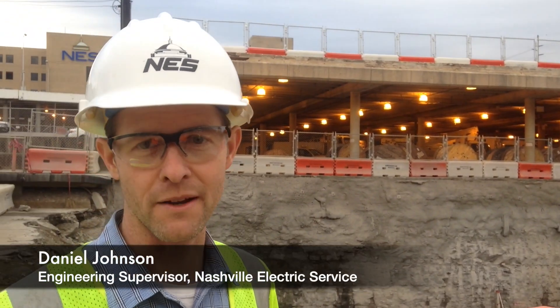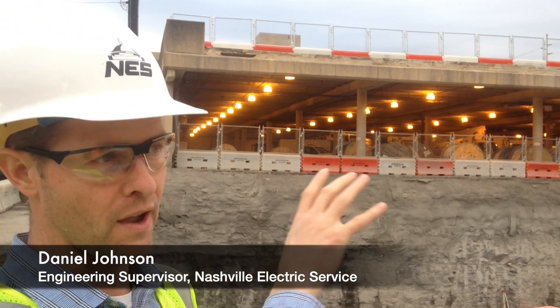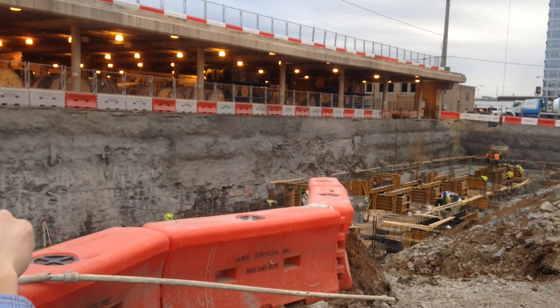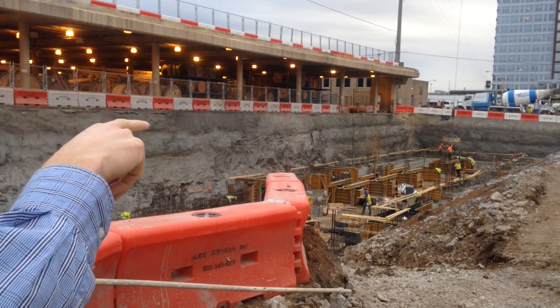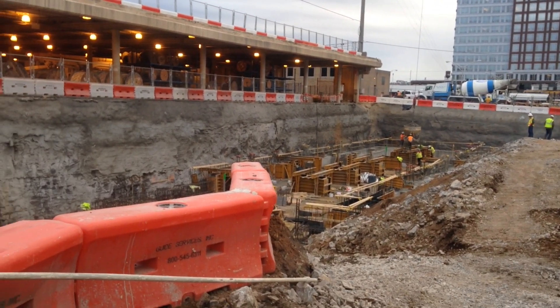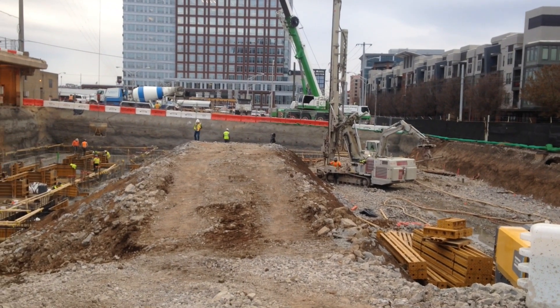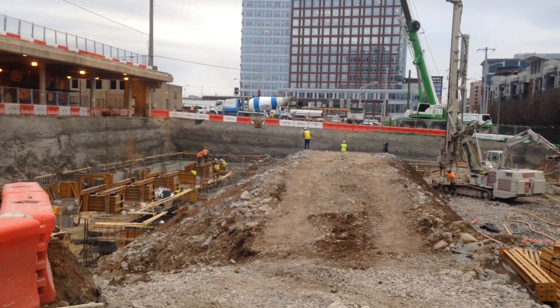The substation is about 220 feet by 135 feet and lines up with our existing parking deck. What they're pouring right now are the basement foundations for our 15 kV switchgear. And what they've already poured are the grade beams on the side of our 69 kV GIS switchgear basement. The area they're working in right there, they're putting in micro piles — this is going to be where our 40 MVA power transformers are going to set, lined up against the street.